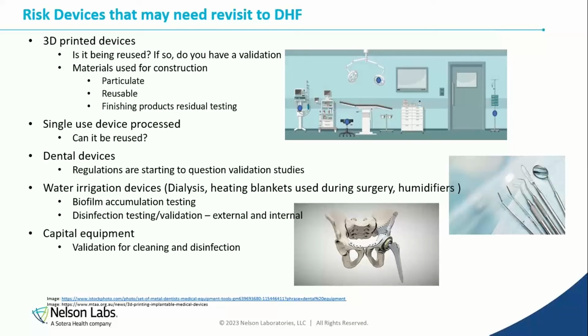And if these machines are sitting for weeks or even days before use, or a week before use, you have to have some sort of process to kill bacteria in there, and they are requiring a disinfection validation. They're asking for a validation for that. So that is your design input validation for your design history file. So just keep that in mind.